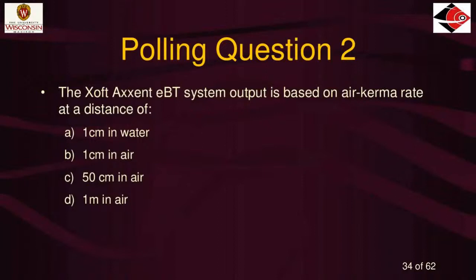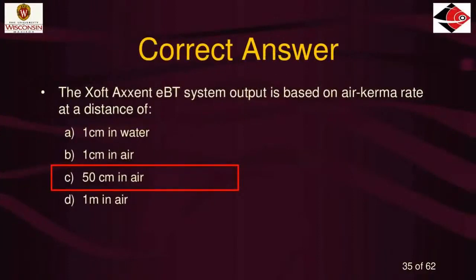This question is up and running in our poll section. The correct answer is C, 50 centimeters in air — that air kerma rate with a subscript of 50 centimeters. A couple of people answered one centimeter in water, which is a little tricky because that's where you finally end up: the dose rate at one centimeter in water. But the output is really based on the air kerma rate at a distance of 50 centimeters in air.